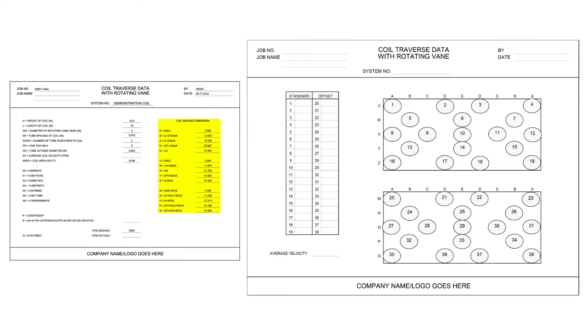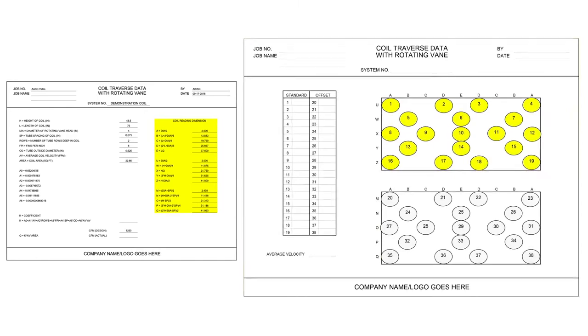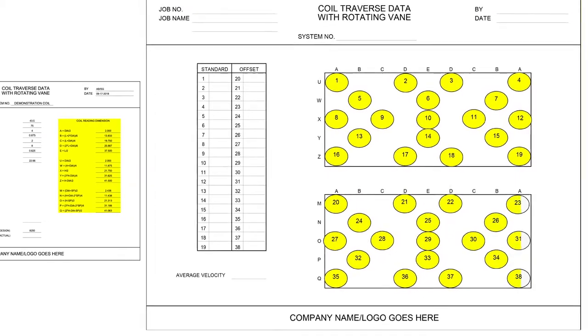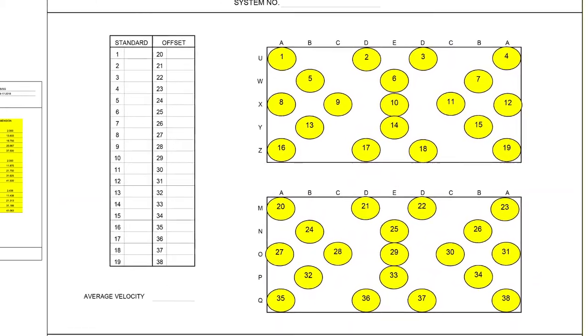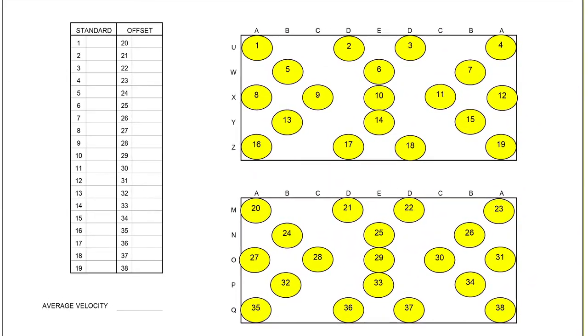These coil reading dimensions are used to measure and mark the 1 through 19 standard velocity reading locations and the 20 through 38 offset velocity reading locations. The vane anemometer positioning diagram is located on page 2 of the coil traverse data with rotating vane form, and these locations are used to position the center of the rotating vane anemometer.